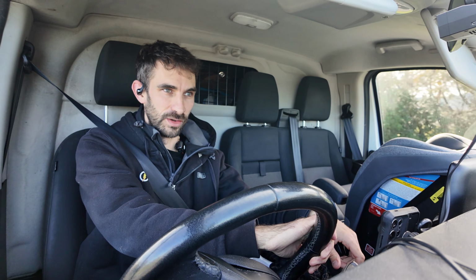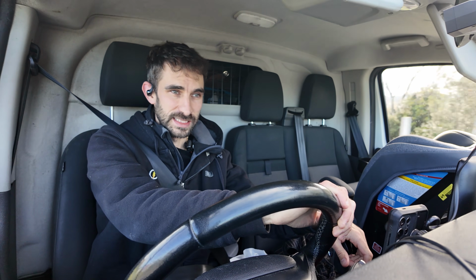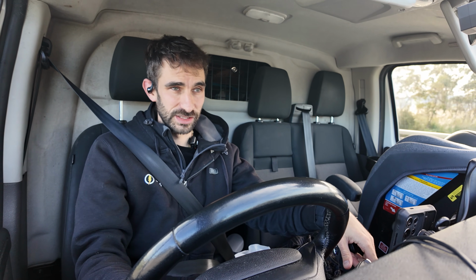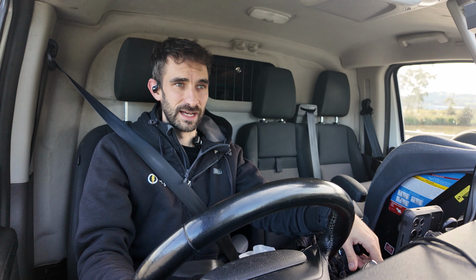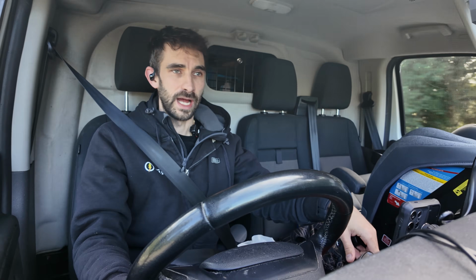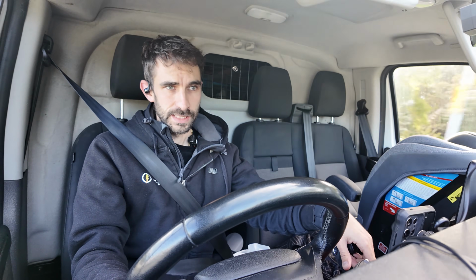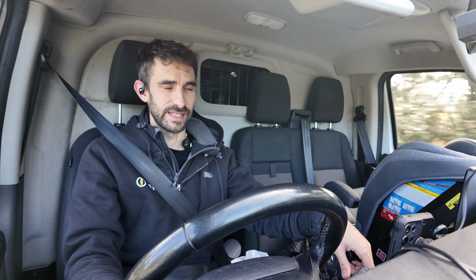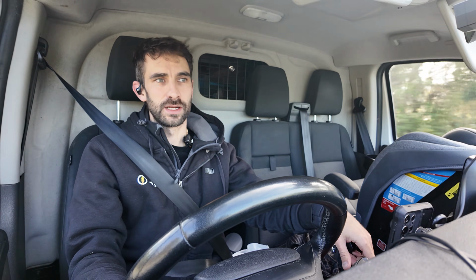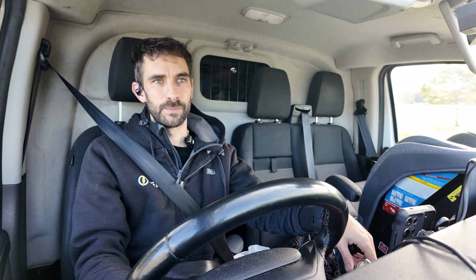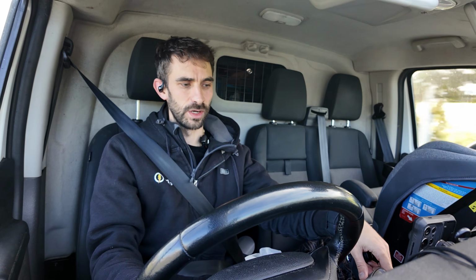Recently, someone did give me one answer of what the earth electrode does, which is protecting against surges. So if you have an 11,000 volt power line fall on your power line and your house gets blasted with 11,000 volts, that earth rod, it doesn't matter about the high resistance, because 11,000 volts is such a high voltage that the resistance doesn't matter.